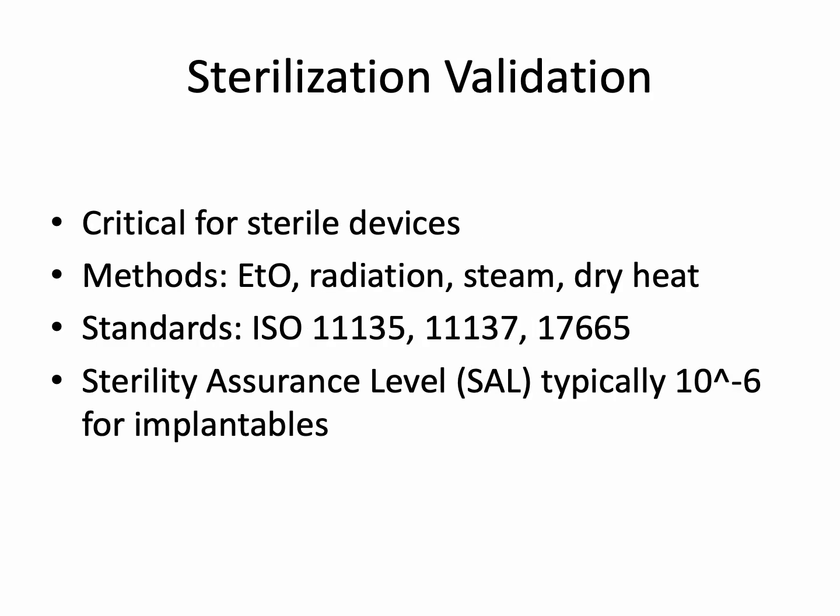For devices marketed as sterile, sterilization validation ensures that the process consistently achieves the required sterility. Methods include ethylene oxide, ETO, radiation, steam, and dry heat sterilization, adhering to ISO 11135, 11137, and 17665 standards.